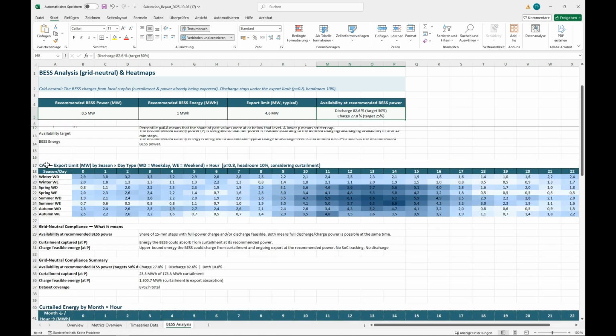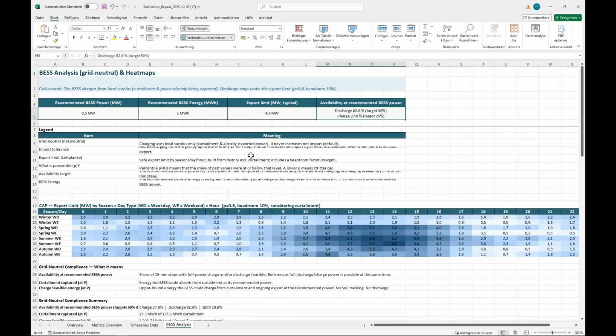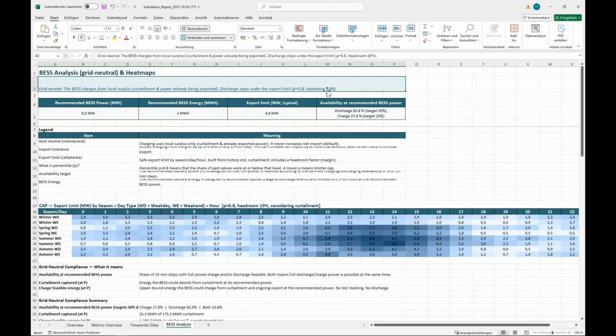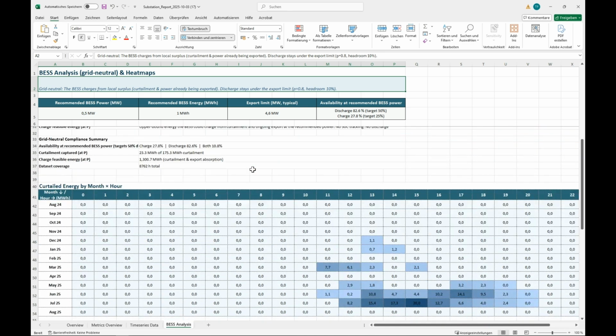We show the export cap at this substation based on different seasons and based on the hours, so we try to always stay within the defined limits. For example, the export limit is the 80th percentile of the generation based on different seasons and weekdays versus weekends, plus a certain safety margin. But you can play around with that—if you want different export limits or a different safety margin, you can change this anytime.